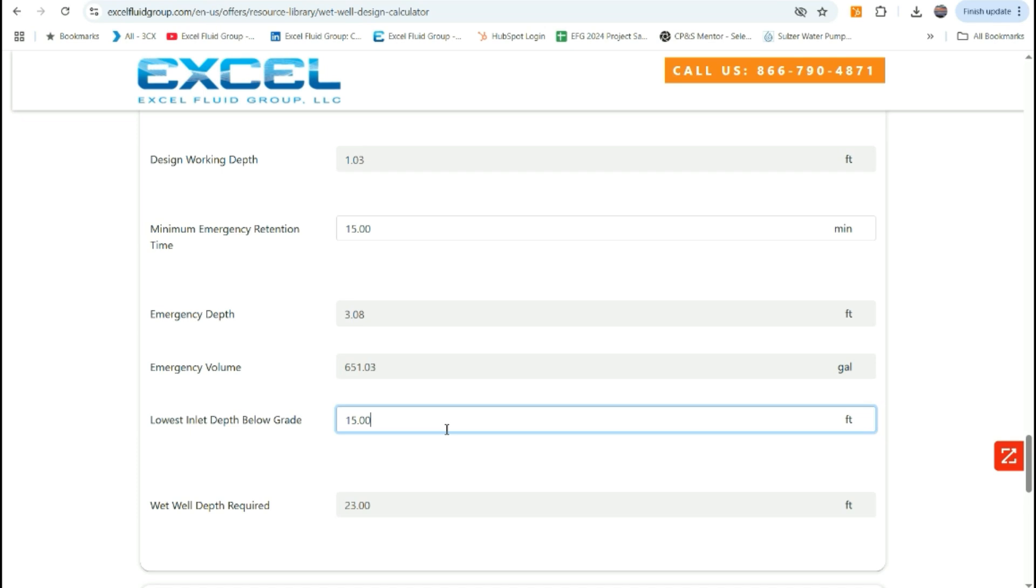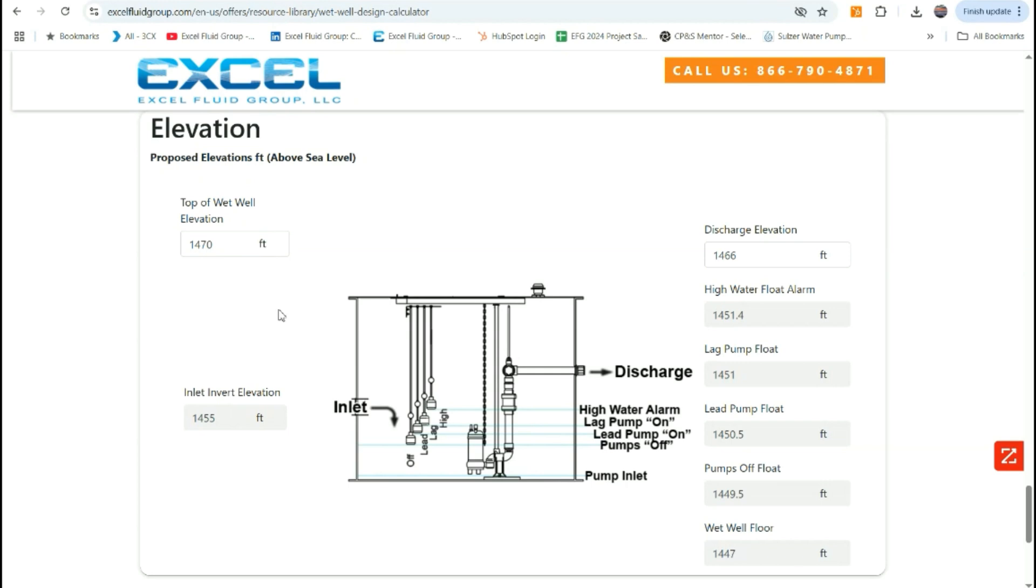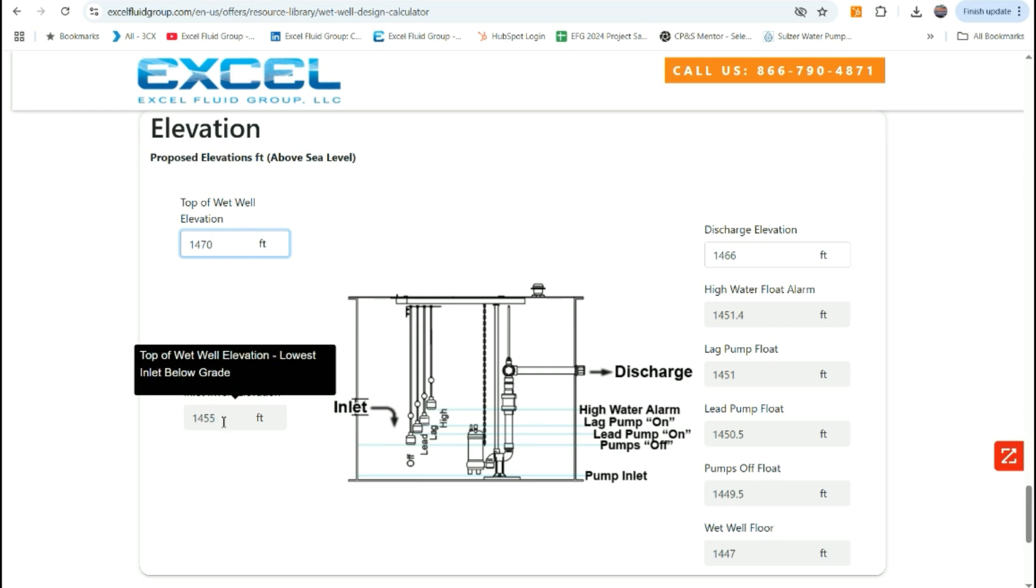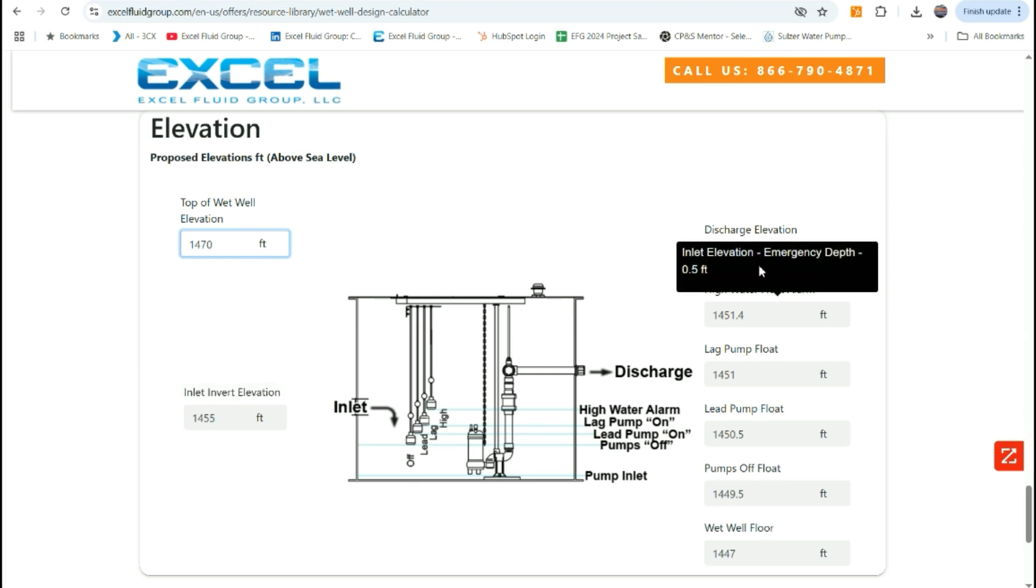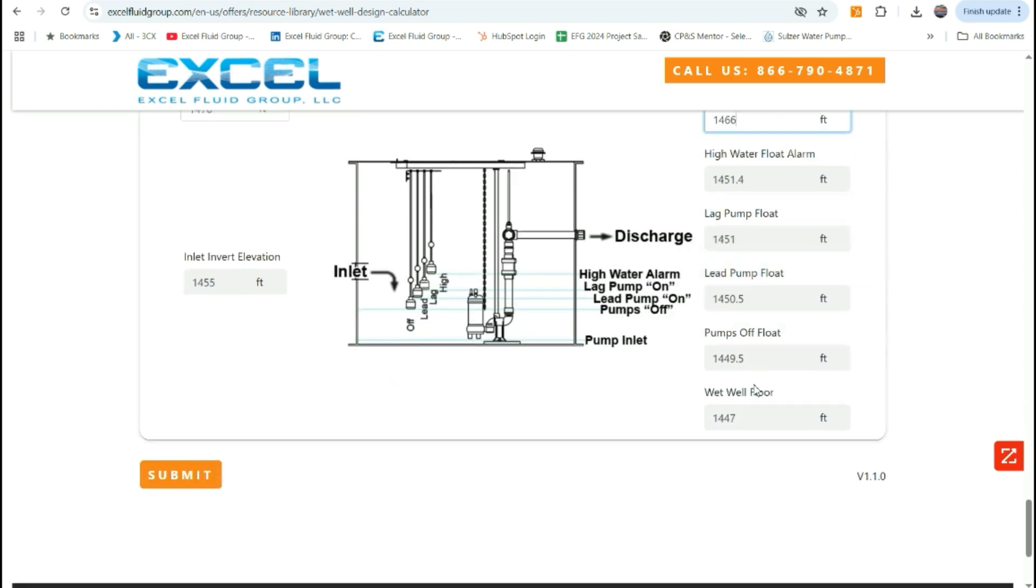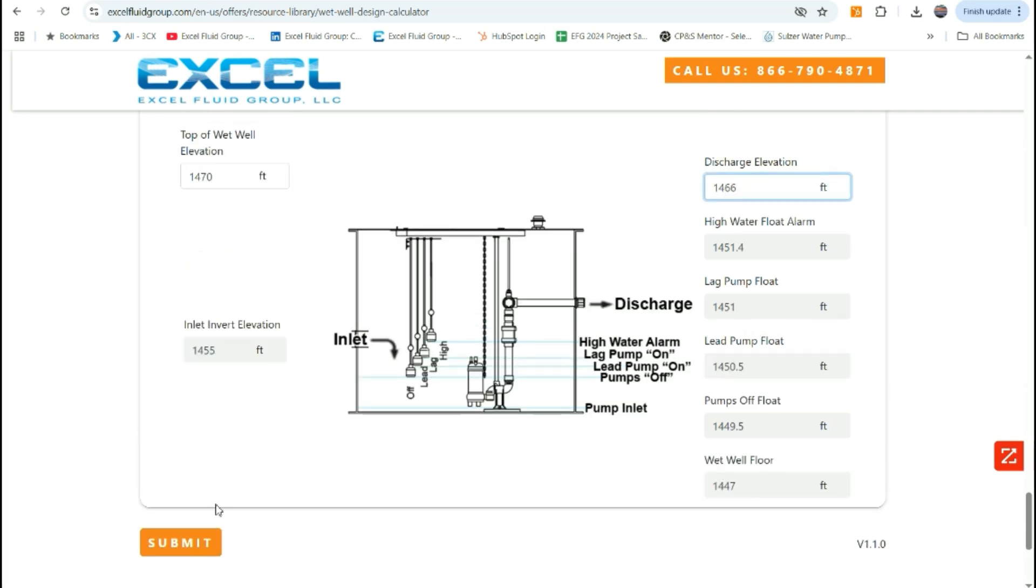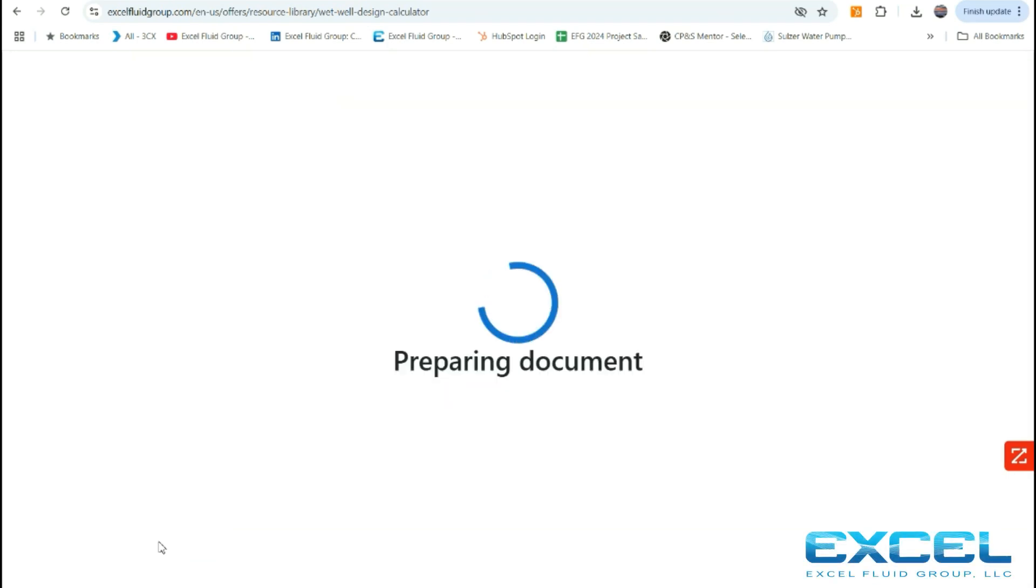Our final input section is for the elevations. You can put in your top of wet well elevation from the force main profile drawing and we will automatically calculate the invert elevation based on previous section. The discharge elevation is also a user input. Generally should be three to four feet below the surface elevation to be below frost line. Once you have that elevation input, the subsequent elevations also calculate based on our standard increments. The pump station could be designed with other increments, but these are our standard. Then once you have all the information input, you can click the submit button.